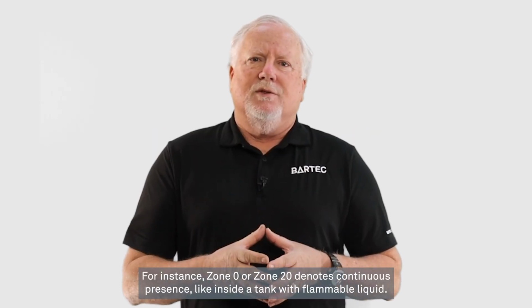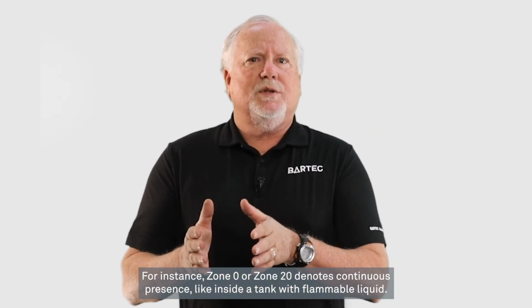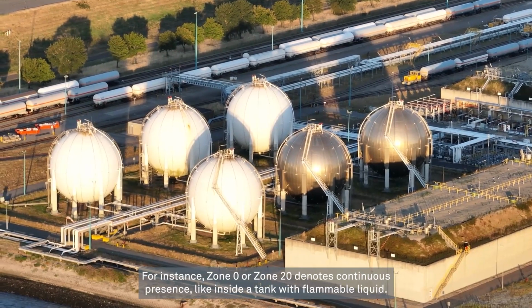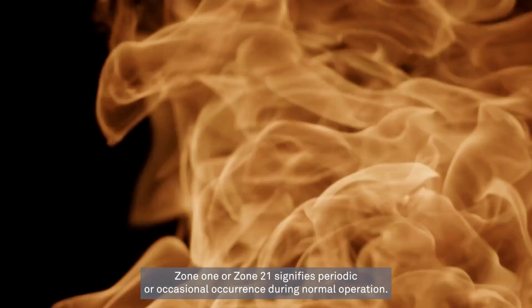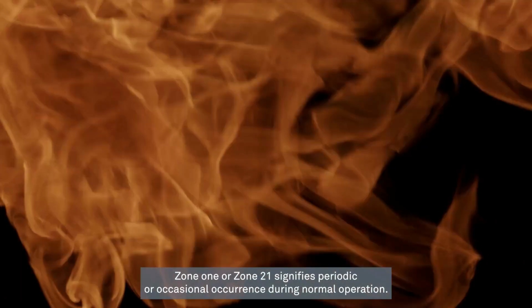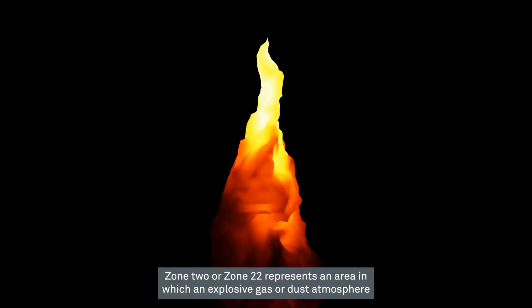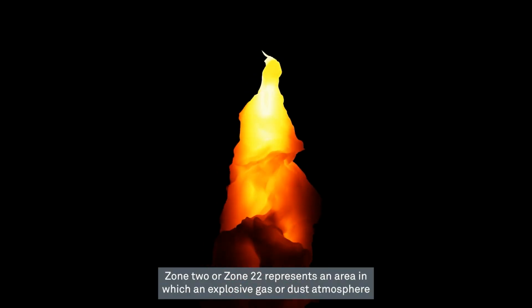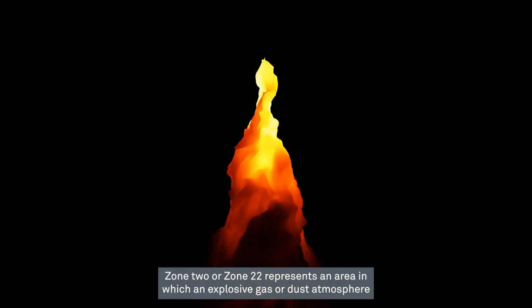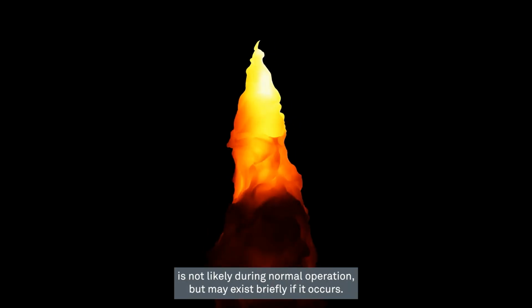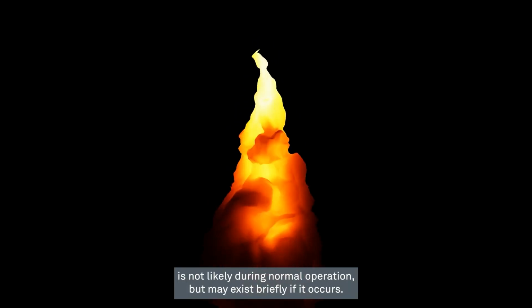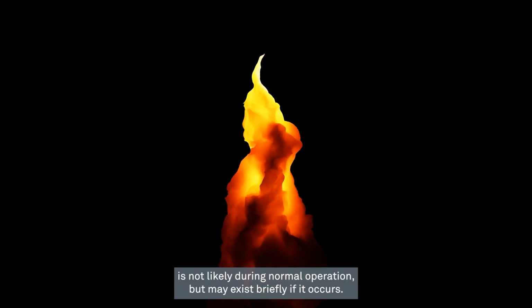For instance, Zone 0 or Zone 20 denotes continuous presence, like inside of a tank with a flammable liquid. Zone 1 or Zone 21 signifies periodic or occasional occurrence during normal operation. Zone 2 or Zone 22 represents an area in which an explosive gas or dust atmosphere is not likely during normal operation, but may exist briefly if it occurs.